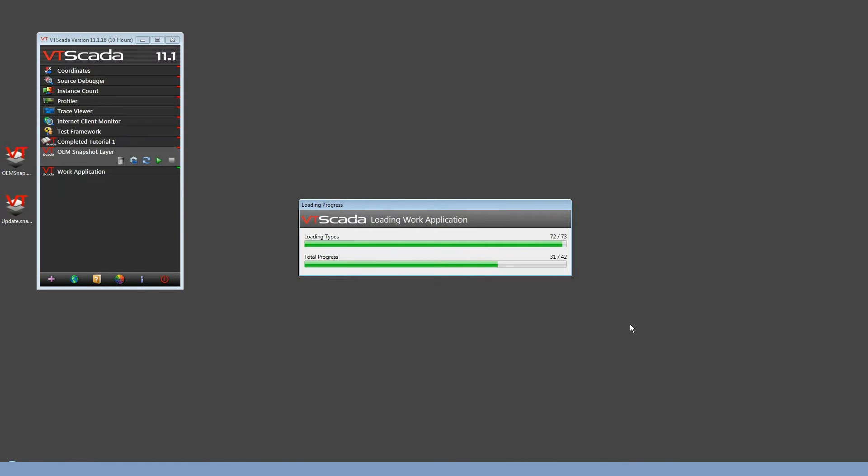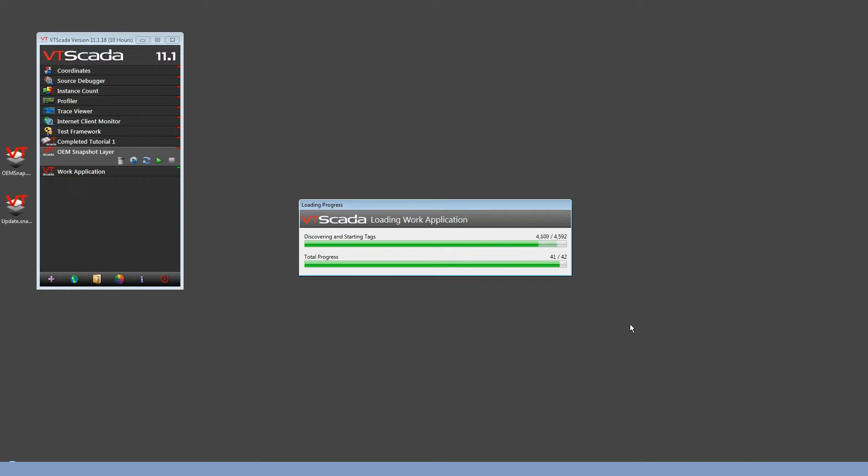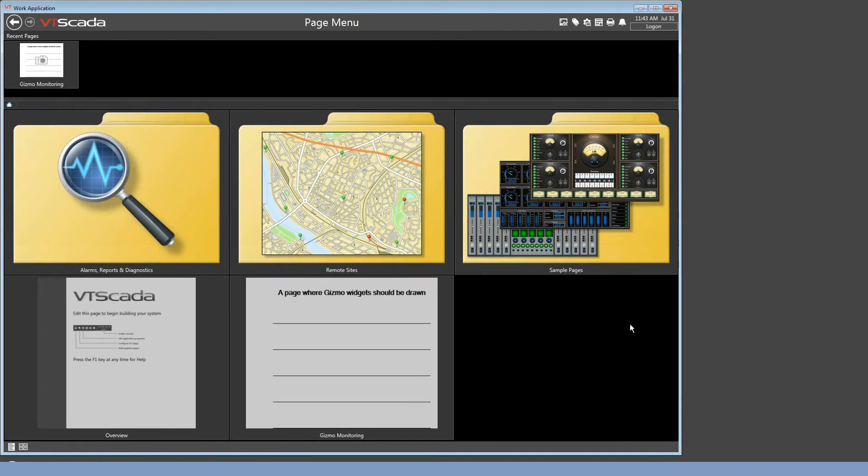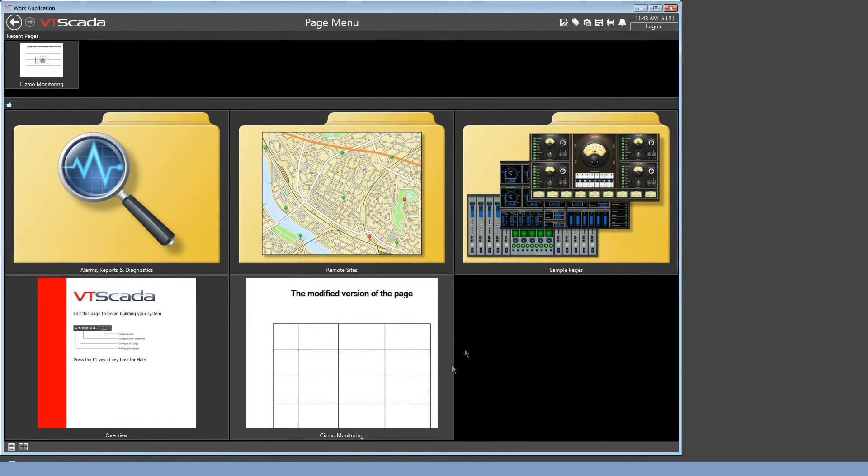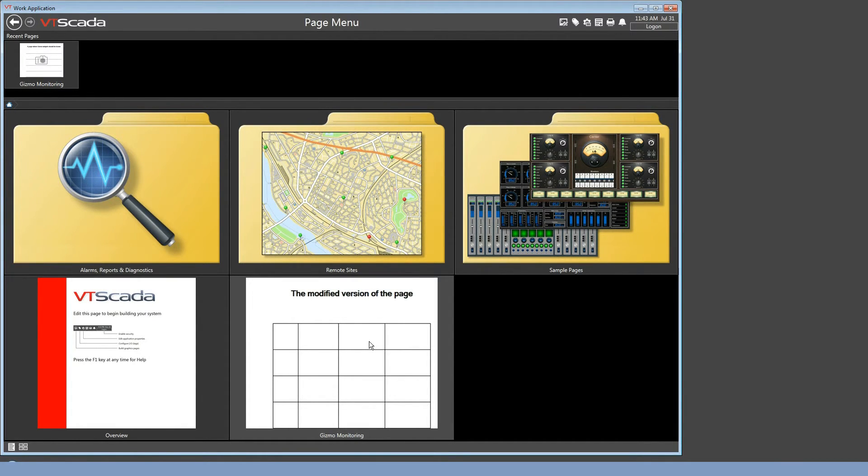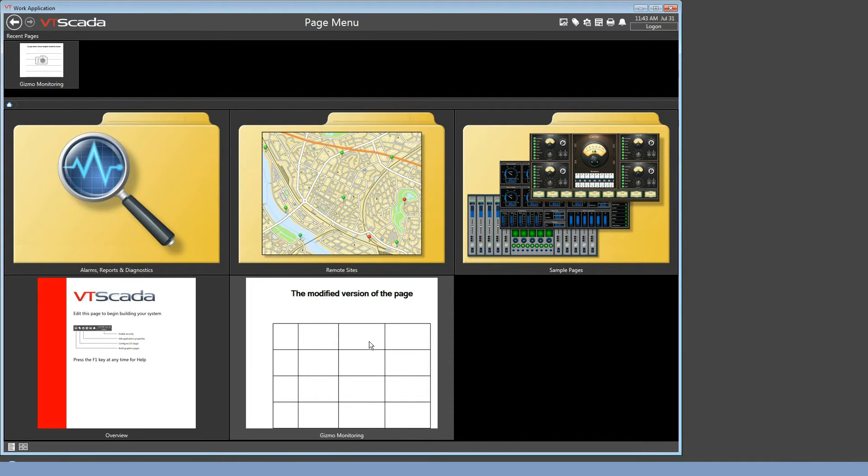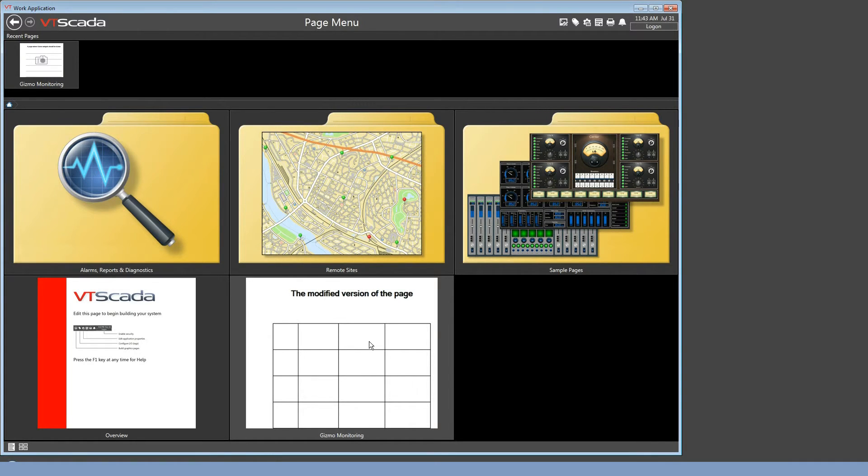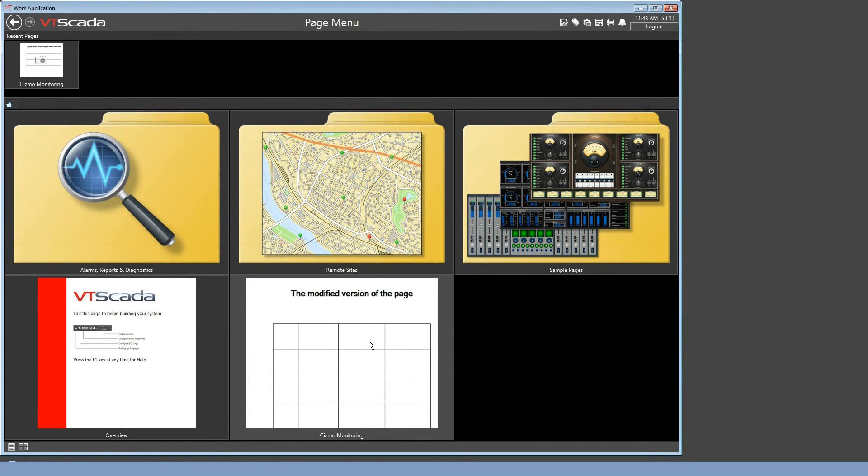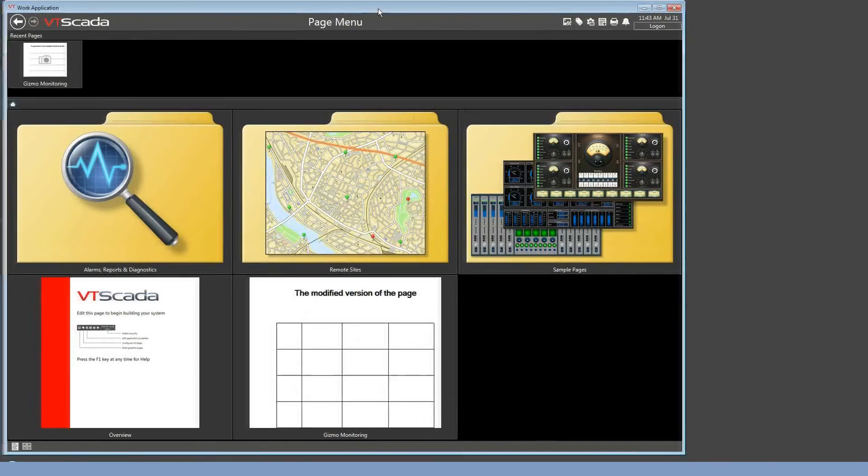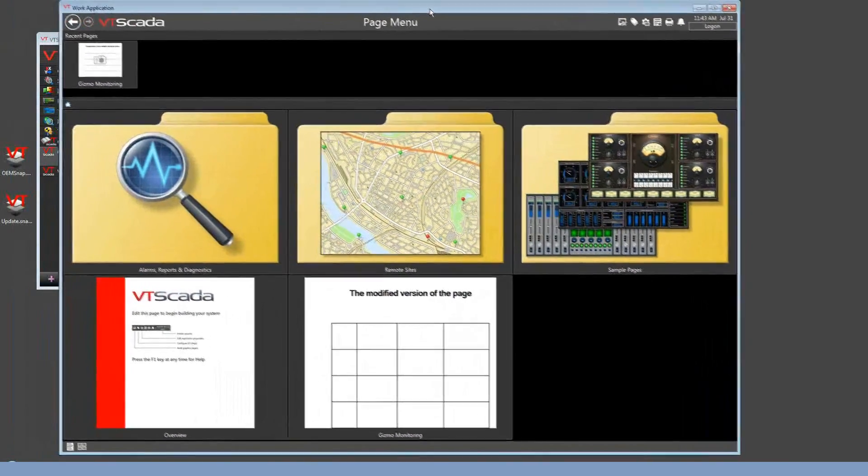We'll see the results of this change in a moment, but as for not being able to edit pages within the working application, if they're defined in the OEM layer, my Gizmo monitoring page is a good example of the wrong way to do things. If I had wanted to provide this sort of a template for people to draw upon, then what I should have done was create that as a widget. Customers could then draw that widget on any new page of their own creation, and then draw whatever they want on top of that. Just remember that your custom pages in your OEM layer are treated the same way as the VT SCADA report page or alarm page, and they won't be available for editing at the customer site.